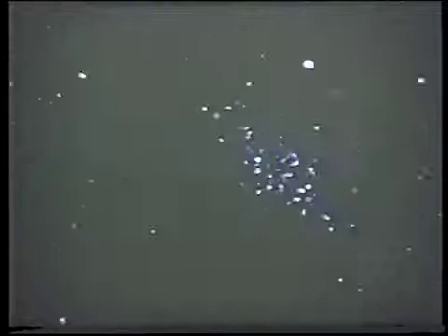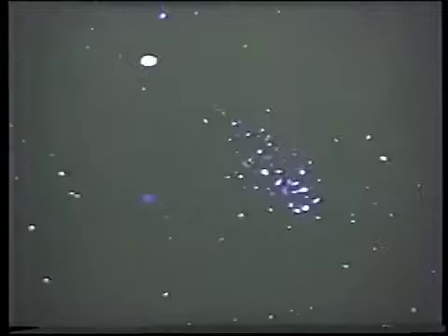So, having reduced the brightness of the source and increased the intensifier gain, we end up with a rather motley collection of spots. We can see some bright ones flaring at different points and can make out the shape of the galaxy near the middle of the screen. The large bright spots are ion events created in the intensifier, and some of the smaller spots are also noise from the intensifier in the form of thermal electron noise. We can verify these noise effects by switching off the source. And only thermal electron and ion spots remain.